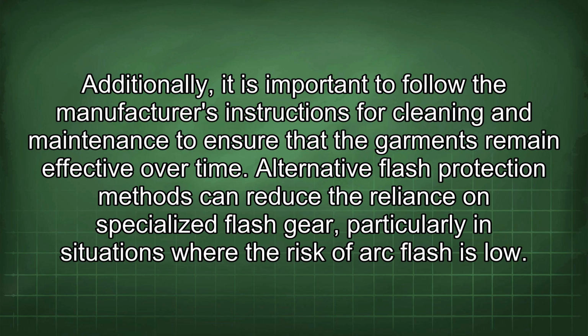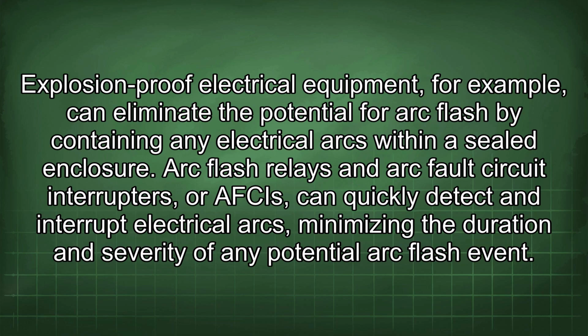Alternative flash protection methods can reduce the reliance on specialized flash gear, particularly in situations where the risk of arc flash is low. Explosion-proof electrical equipment, for example, can eliminate the potential for arc flash by containing any electrical arcs within a sealed enclosure. Arc flash relays and arc fault circuit interrupters, or AFCIs, can quickly detect and interrupt electrical arcs, minimizing the duration and severity of any potential arc flash event.